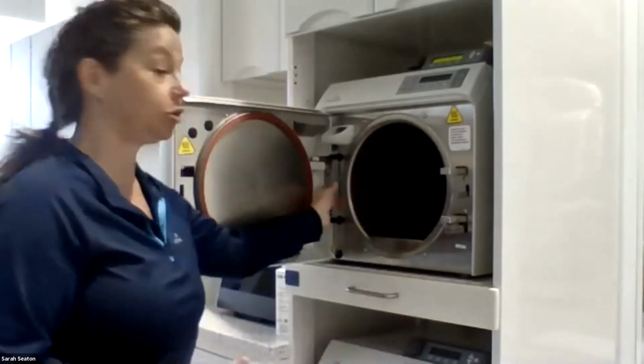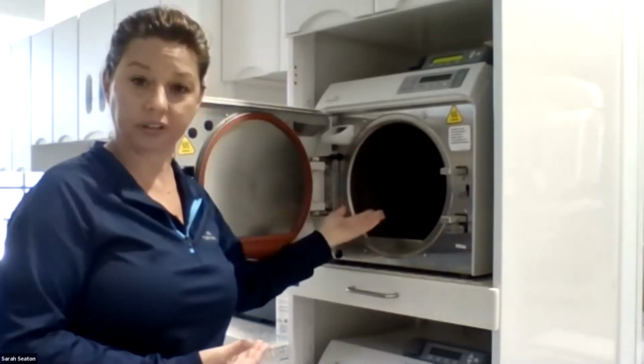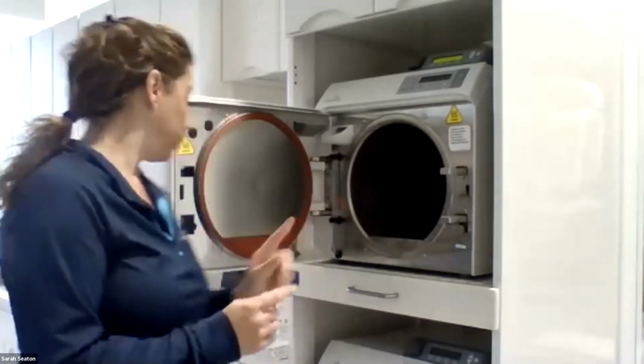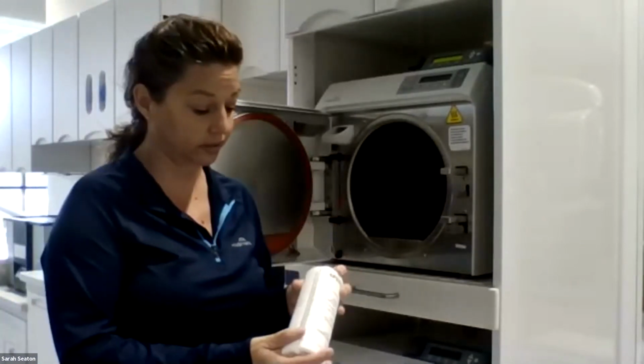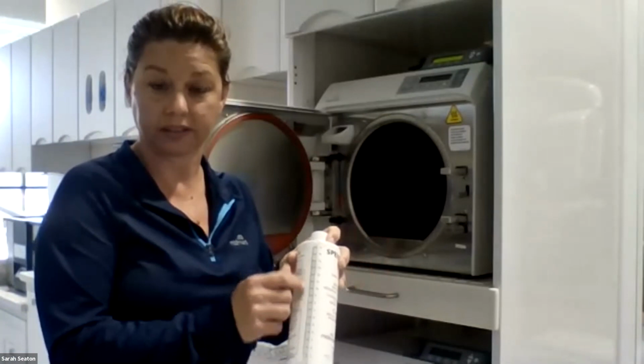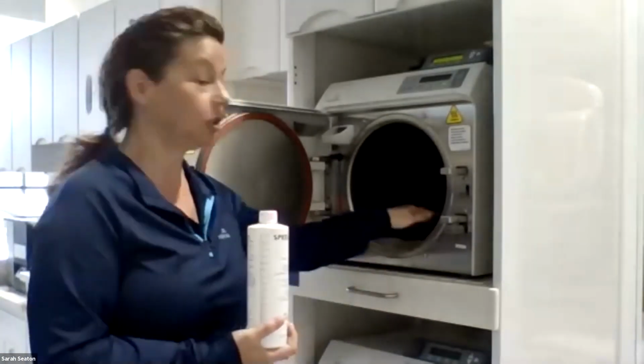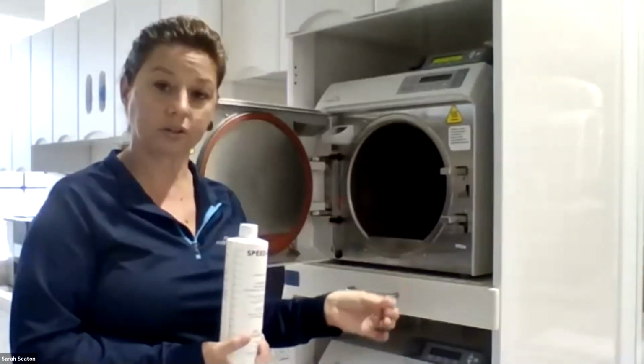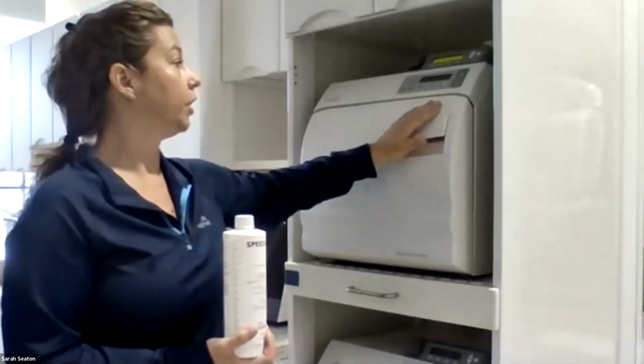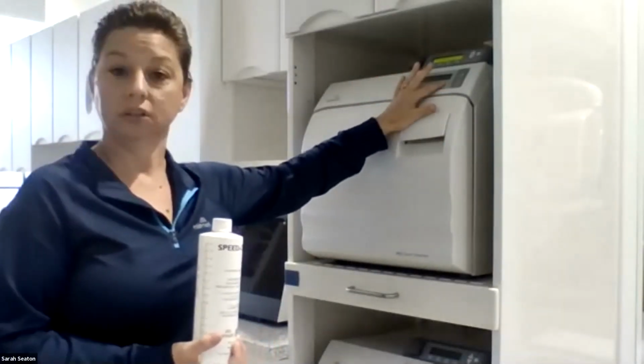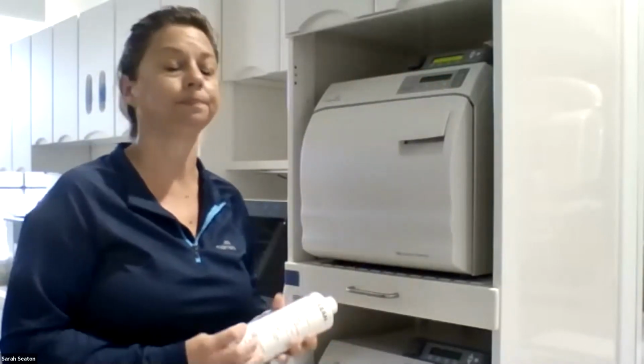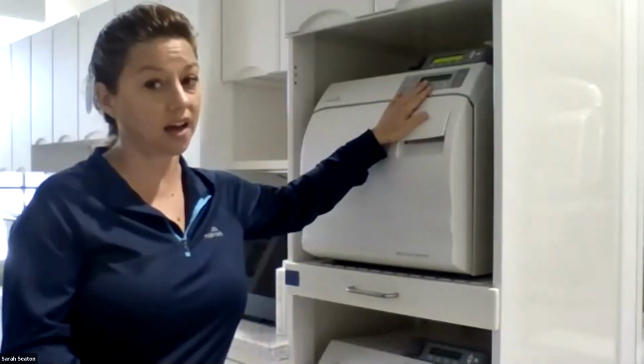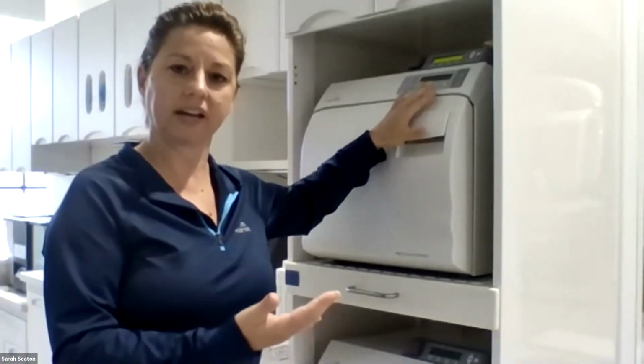So for the first step, we're gonna flush the system. We'll start out by draining the dirty water out of the reservoir and refilling it with clean distilled water. Once you've done that, you need to pour 1 ounce, and the ounces are clearly defined on the Speed Clean bottle, 1 ounce of Speed Clean directly into the bottom of the chamber, okay? Once you've done that, we'll go ahead and select a pouch cycle to run it through. That'll clean your valves internally. Before it gets to the drying portion of the cycle, because it doesn't need to dry in order just to clean those internal valves, you're going to press stop. It saves time. So once you've done that, gone through the pouch cycle, press stop.